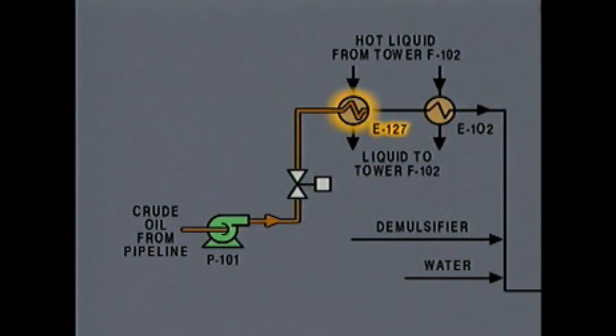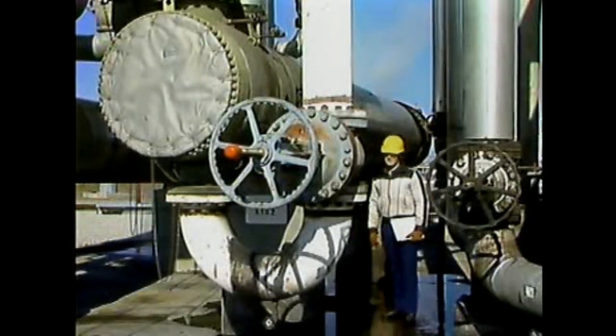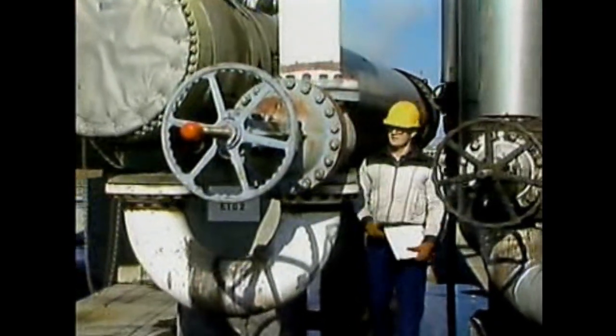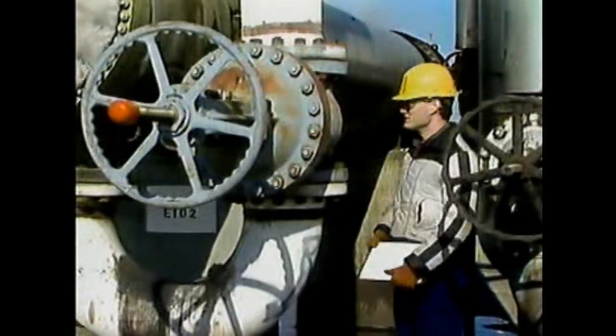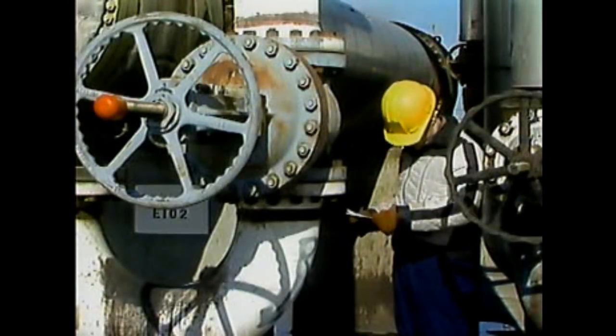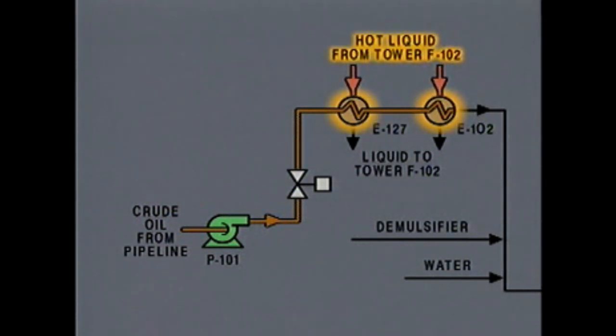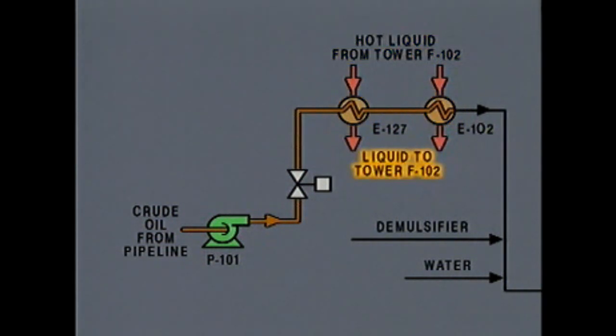From heat exchanger E-127, the oil goes to another heat exchanger labeled E-102. You can find this second heat exchanger by locating the line from the tube side outlet of heat exchanger E-127 and following it to the tube side inlet of heat exchanger E-102. The diagram indicates that the heat added to the oil in the heat exchangers comes from hot liquid from distillation tower F-102. When the liquid leaves the heat exchangers, it returns to the tower.